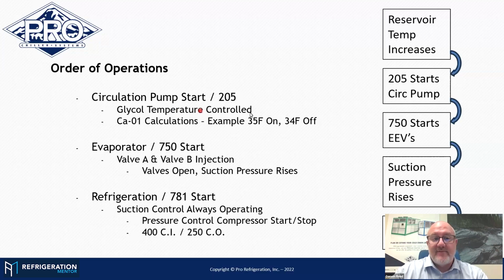circulation pump based off of the temperature of the glycol reservoir. We use a calculation for that. That's part of the control software. So we're monitoring the glycol reservoir. An example would be if the glycol temperature gets above 35, I turn on the circulation pump. Once I turn the circulation pump on, that's sending a signal to the 750, which is the evaporator controller, and it's saying, hey guys, I'm running a pump. You should start making an adjustment with my valves. So start waking up valve A and valve B in an injection mode.